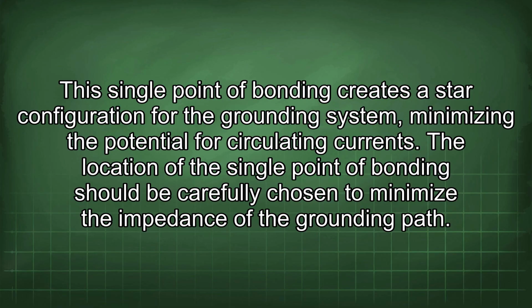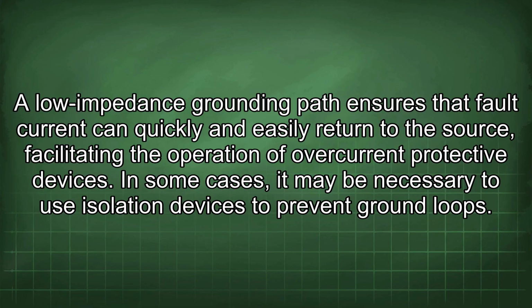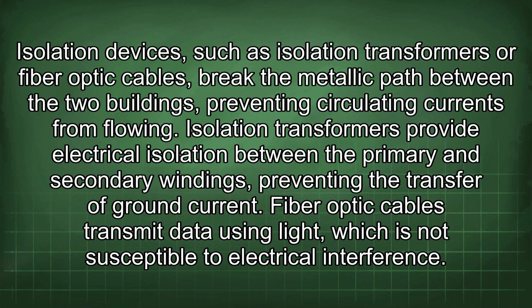The location of the single point of bonding should be carefully chosen to minimize the impedance of the grounding path. A low impedance grounding path ensures that fault current can quickly and easily return to the source, facilitating the operation of overcurrent protective devices. In some cases, it may be necessary to use isolation devices to prevent ground loops. Isolation devices, such as isolation transformers or fiber optic cables, break the metallic path between the two buildings, preventing circulating currents from flowing. Isolation transformers provide electrical isolation between the primary and secondary windings, preventing the transfer of ground current. Fiber optic cables transmit data using light, which is not susceptible to electrical interference.